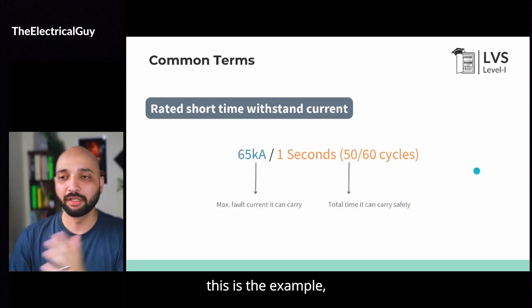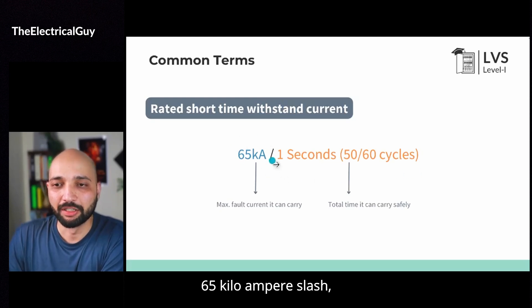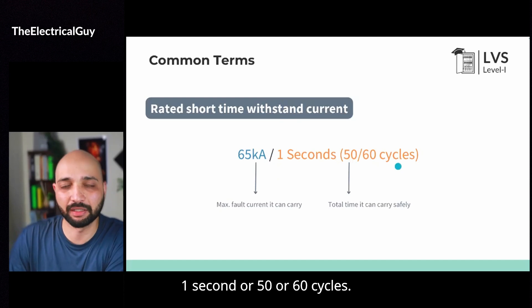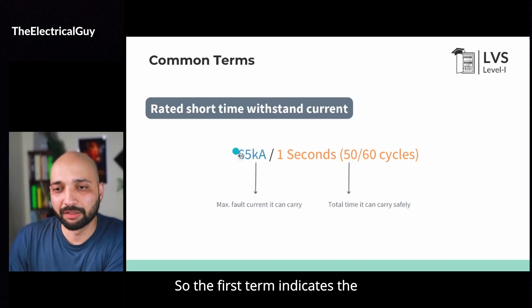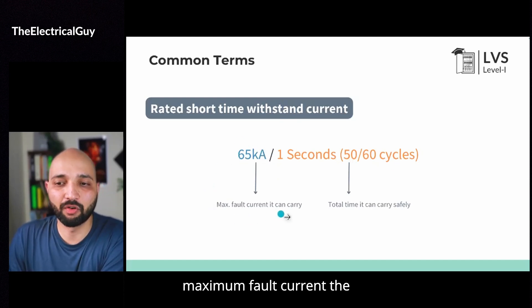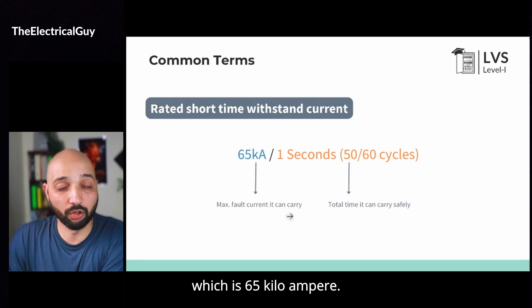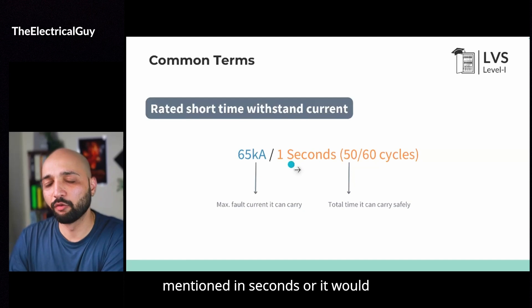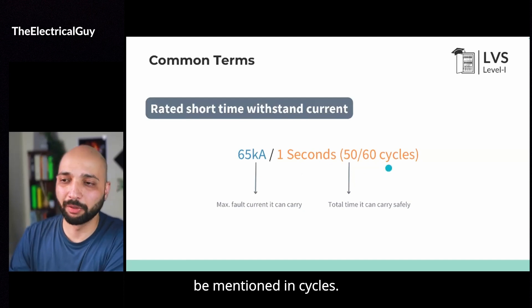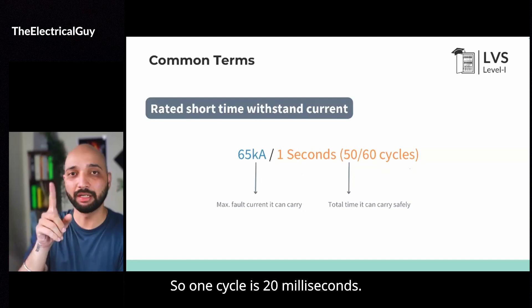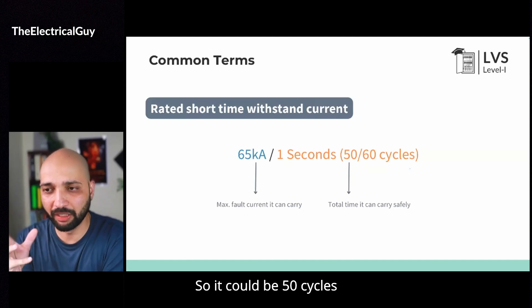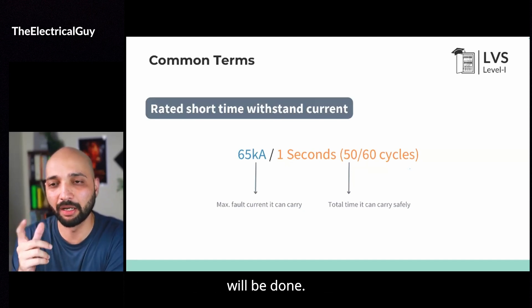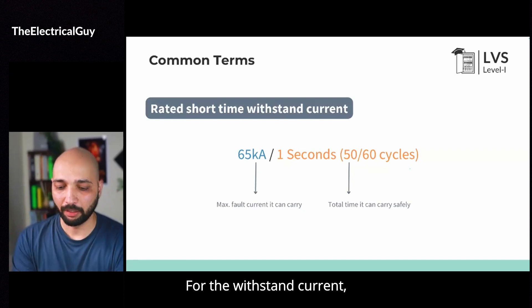So that is rated short time withstand current. Here is the example of how you will see it represented: you may find 65 kA / 1 second, or 50 or 60 cycles. The first term indicates the maximum fault current the switchgear can carry, which is 65 kA, and for how much time — it could be 1 second, or it would be mentioned in cycles, where 1 cycle is 20 milliseconds, so it could be 50 cycles or 60 cycles. This is how the representation will be done for the withstand current.